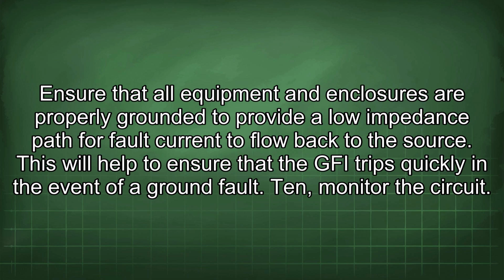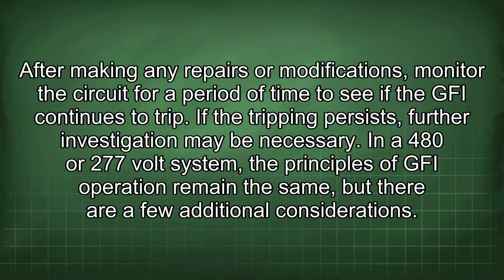10. Monitor the circuit. After making any repairs or modifications, monitor the circuit for a period of time to see if the GFI continues to trip. If the tripping persists, further investigation may be necessary.